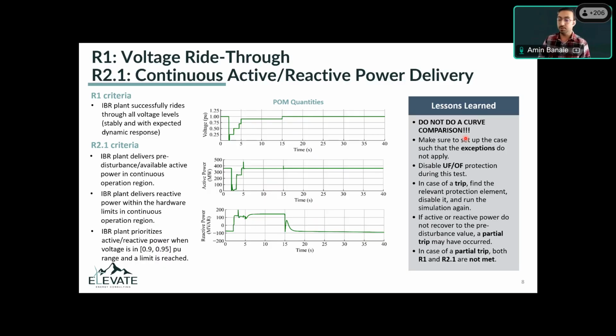So this is an approach that I've seen a lot, that people put the PRC-29 LVRT curve on a figure and then put the under voltage and over voltage protection settings of, let's say, inverter and the feeder relays and HV relays on the same curve, and then say that, okay, if the relay curves are outside the PRC-29 curve, then it's a compliance. And that's not technically correct, since each of those voltage curves are at different locations across the plant. And you need to take into account the voltage variation, or voltage increase or drop, that the impedances across the plant are going to cause and shift those curves around.